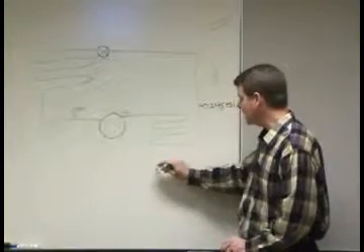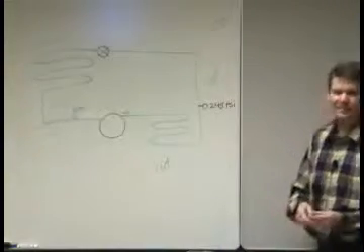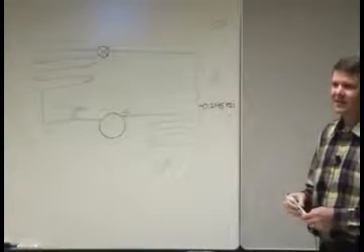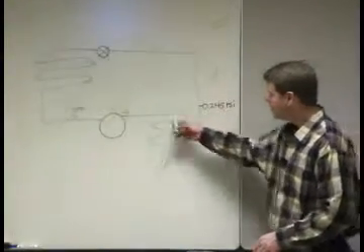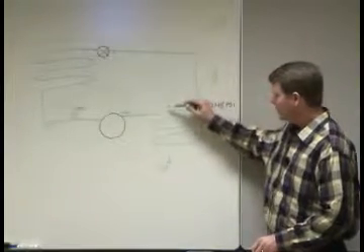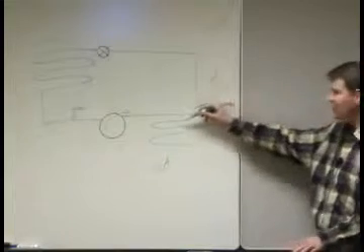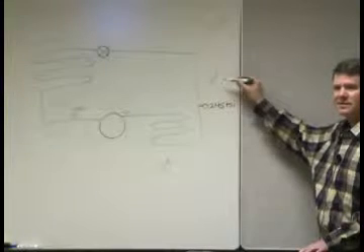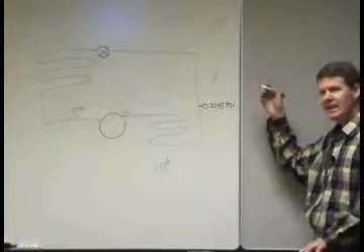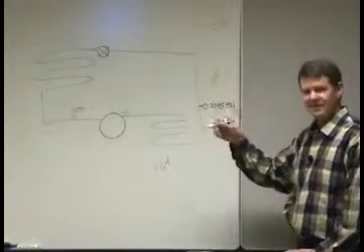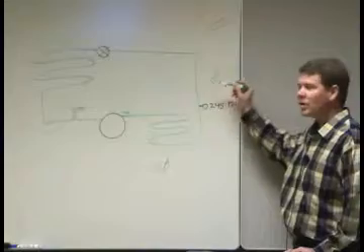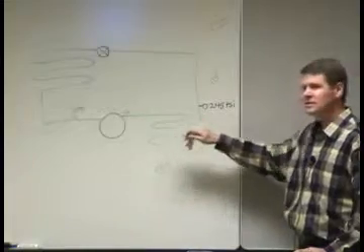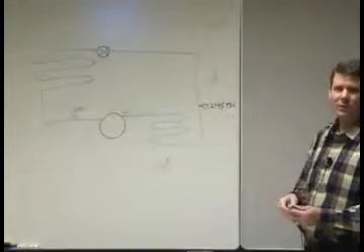This coil is outside, on the side of your house. Say it's an 80-degree day, 85-degree day. We're blowing 85-degree air across this coil, and we've got this Freon going through that has a boiling point of 115 degrees. What's going to happen? Any guesses? Gonna condense. That's right. Since our 80 degrees is colder than 115, we're going to take heat out of this refrigerant, and it's going to condense back into a liquid.